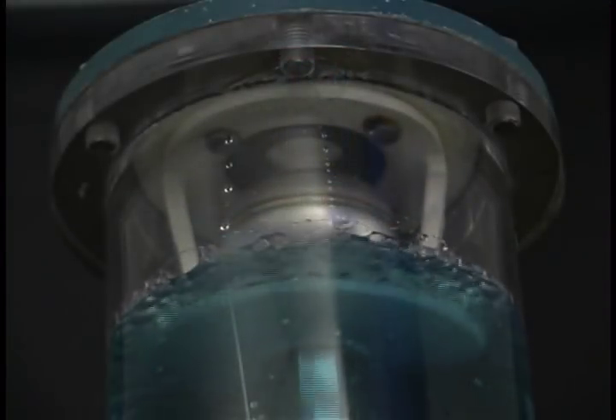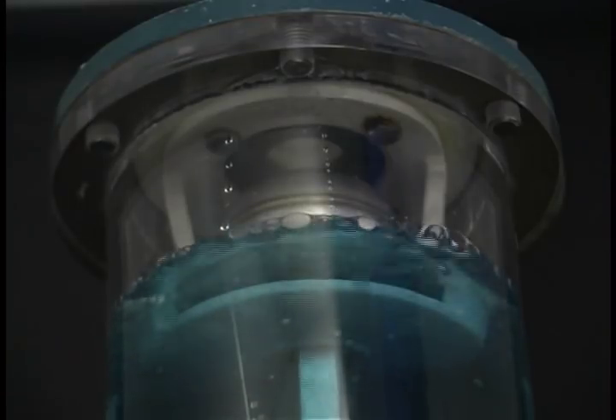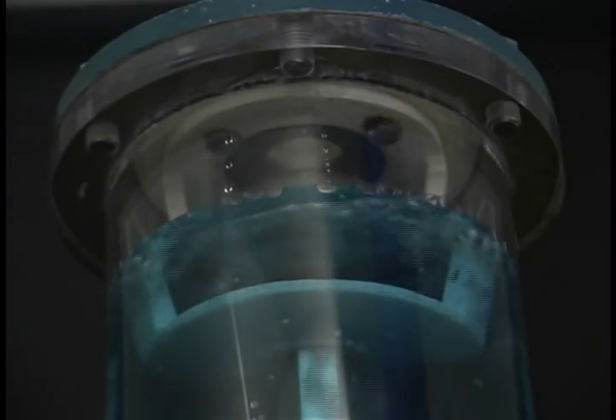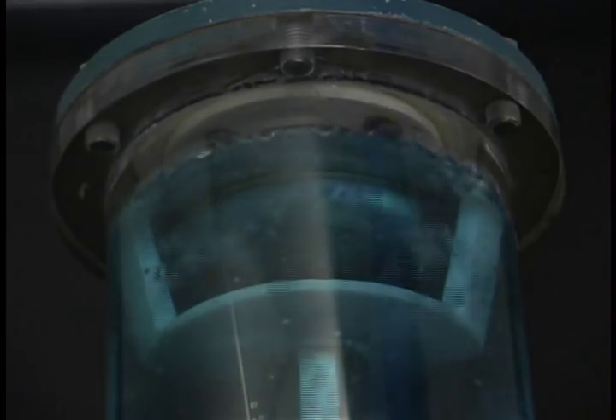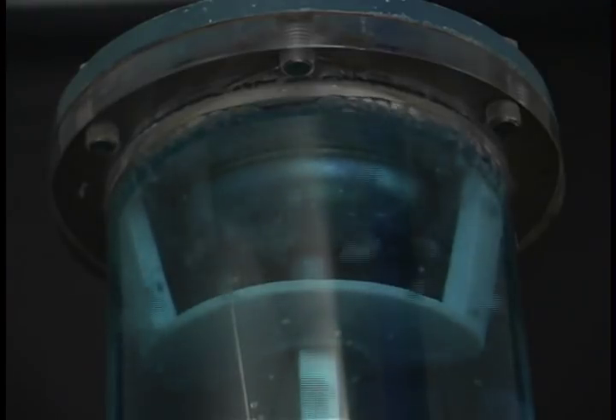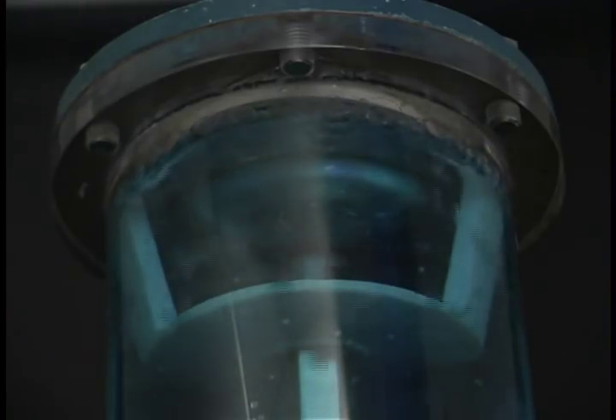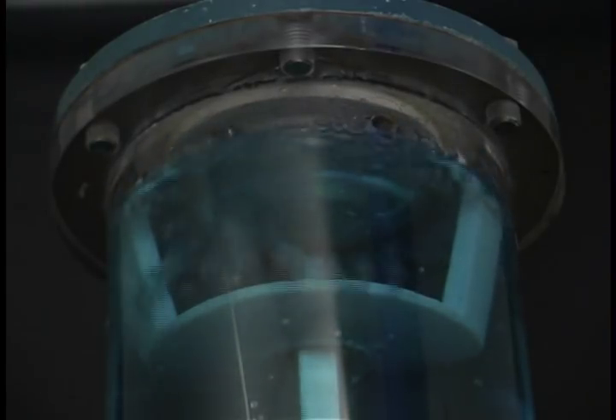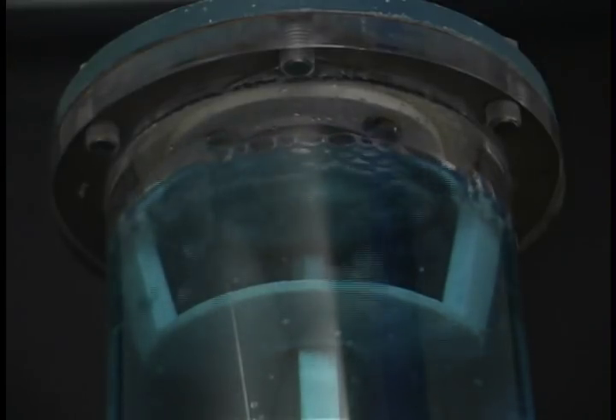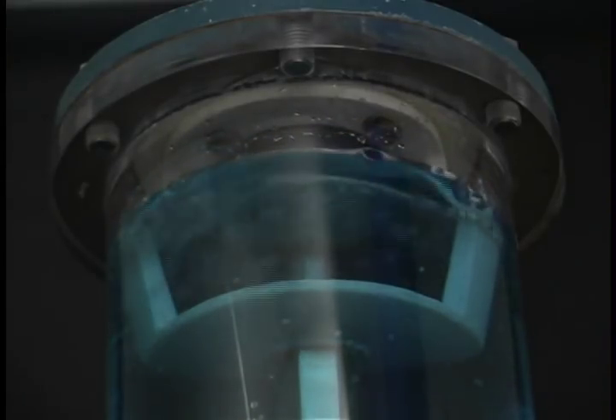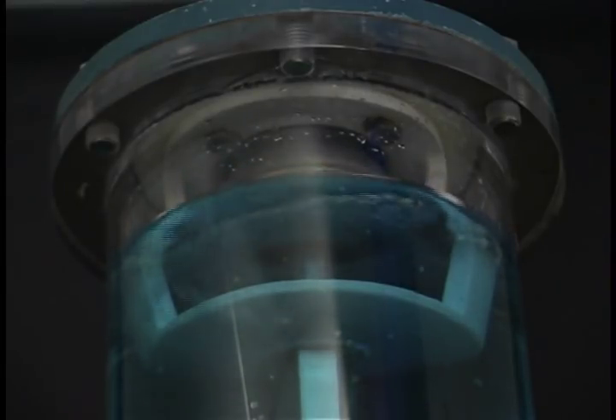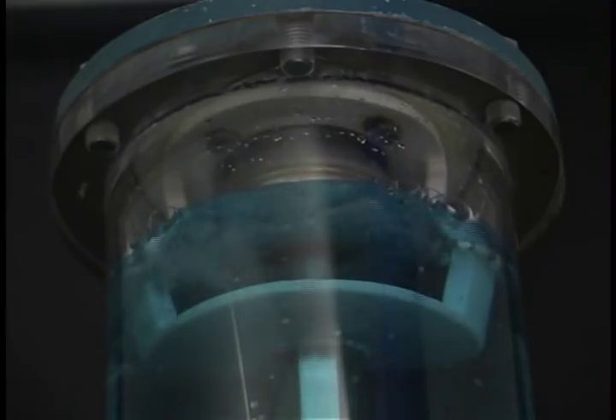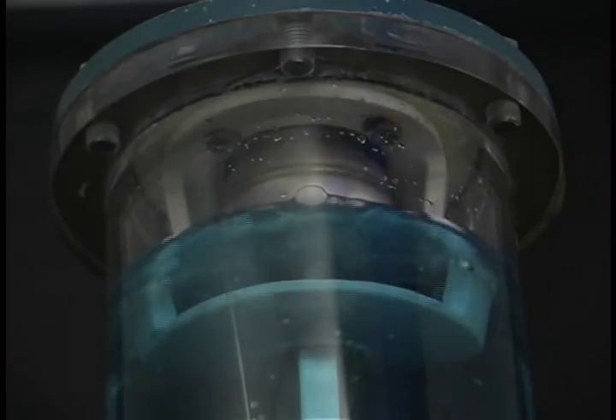A close-up shows the water entering the valve, raising the float into the resilient seat and closing the valve. The float and float stem are guided by a hexagonal float guide. This assures positive seating of the float and protects it from colliding against the interior of the valve. All Valmatic air valve floats are manufactured with heavy duty type 316 stainless steel and all floats are guaranteed for the life of the valve. Air vacuum valves are available in sizes half inch through 20 inch and have inlets and outlets of the same diameter.